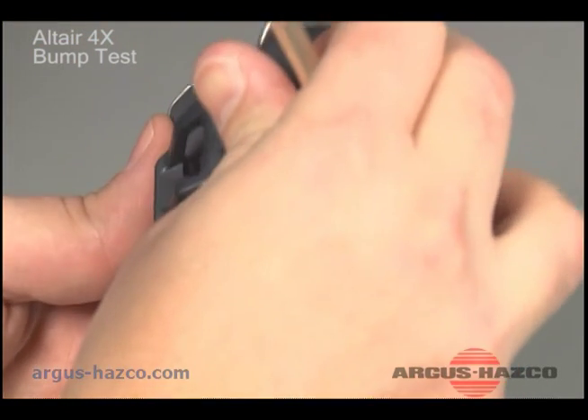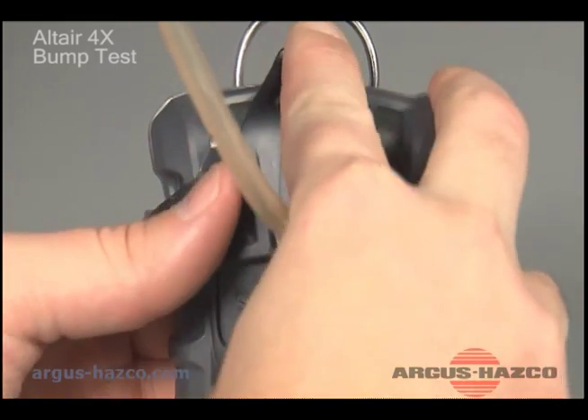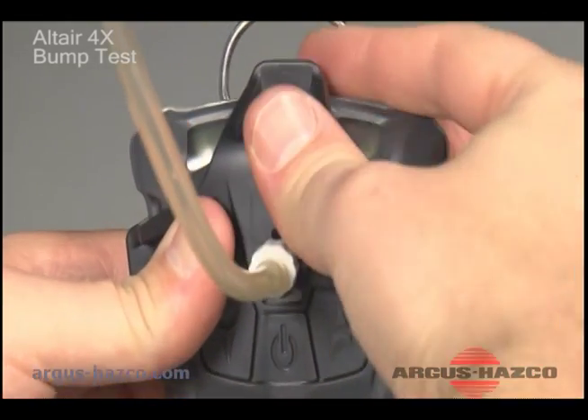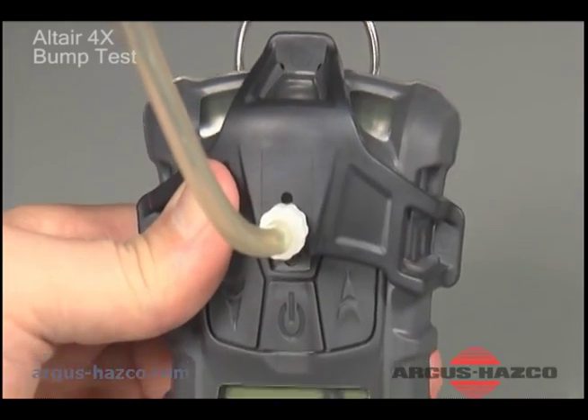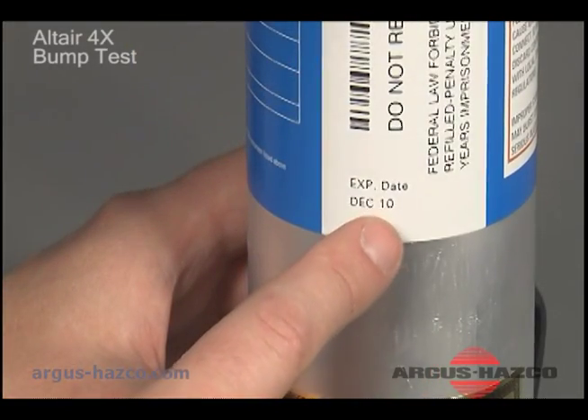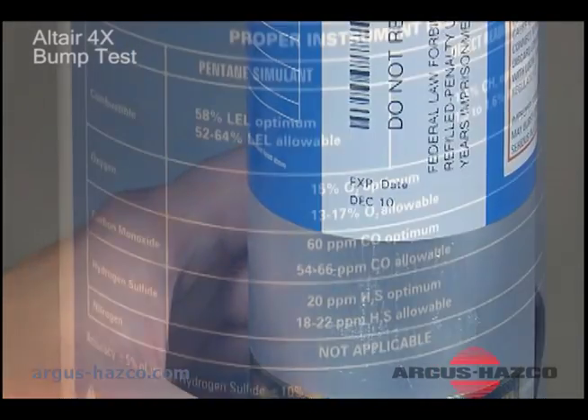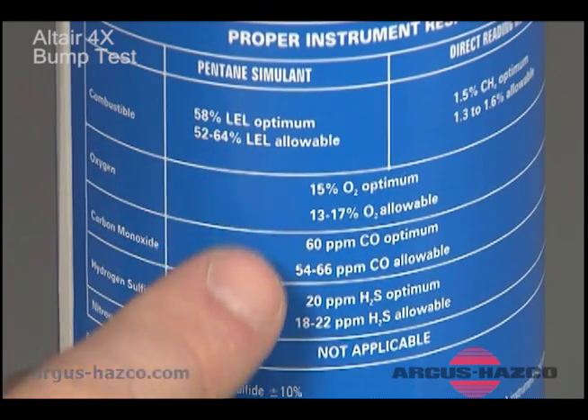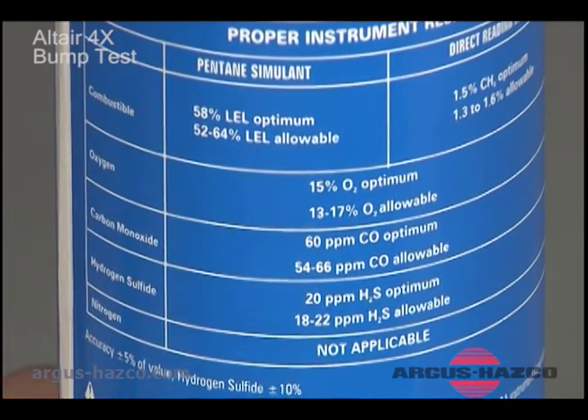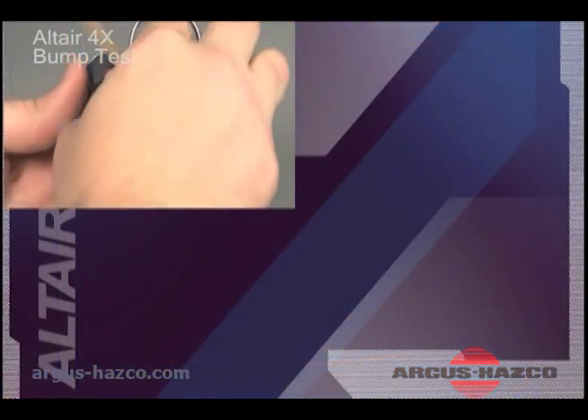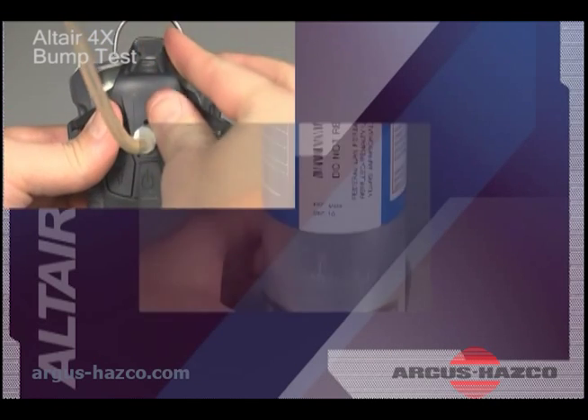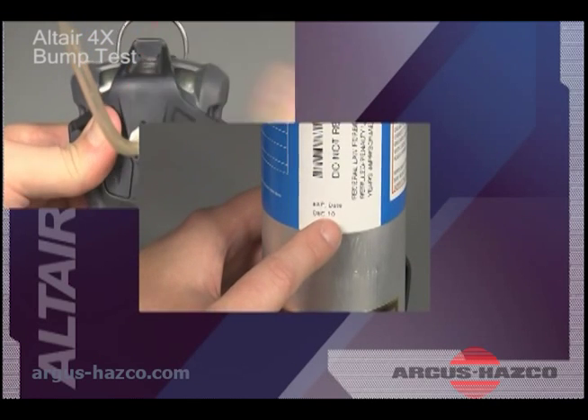Many times, bump test failures are caused by simple issues. Some common causes are a calibration cap that is not seated correctly, bump test gas that is past its expiration date, or bump test gas concentrations that do not match those for which the instrument is set up. If these issues have been verified and resolved and the detector still fails the bump test, the unit must perform a full calibration.